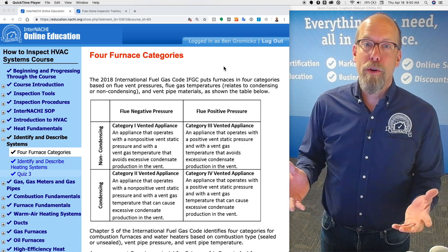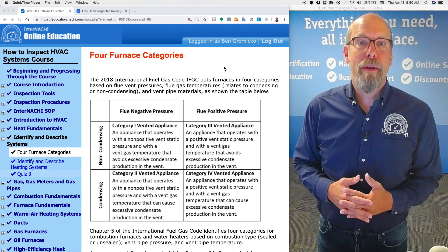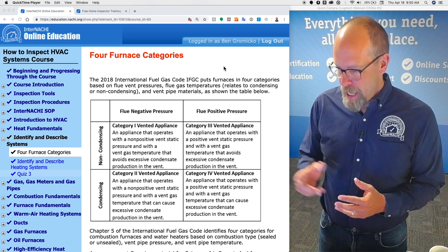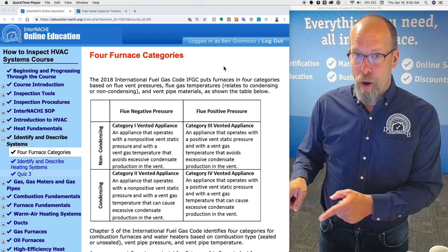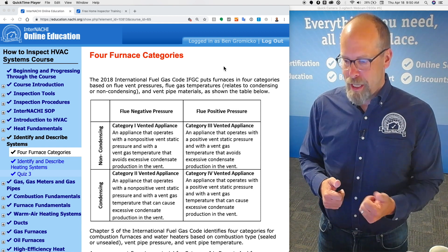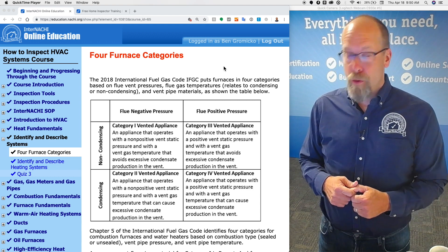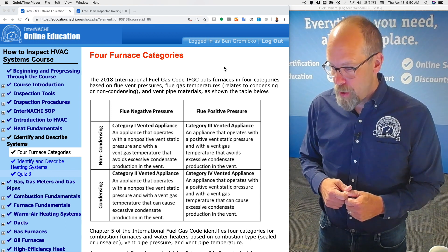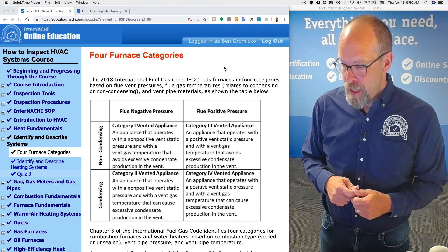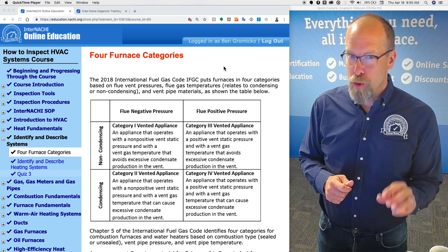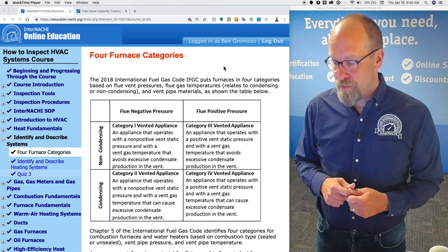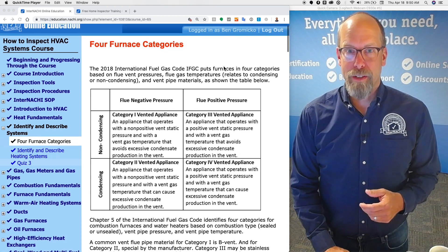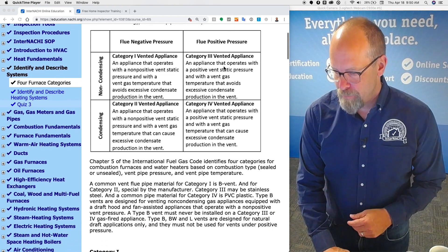Category four vented appliance is pretty common for us home inspectors to find. It's in that bottom right corner, so we have a flue positive pressure and it's condensing. A category four vented appliance operates with a positive vent static pressure and with a vent gas temperature that's cool, that can cause excessive condensate production in the vent. So that furnace is going to collect and discharge that condensate.